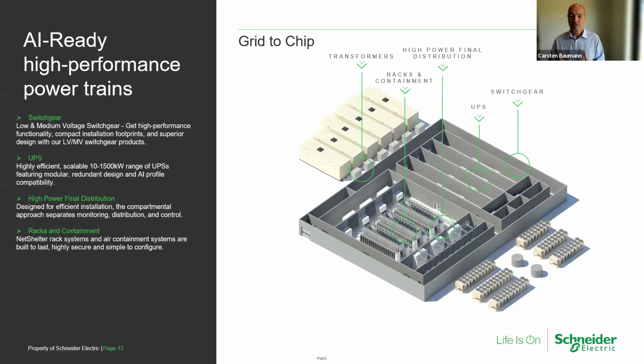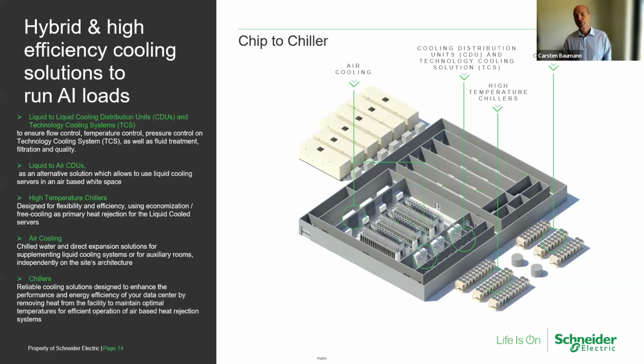And now with AI, we're actually seeing that it's not so much that the power can go out. These AI training sessions happen in about 7 minute intervals, and then they ramp down, and then they go into saving and data validation mode. However, if you do not continue to cool those chips, they can literally physically crack and destroy themselves. So therefore, there are different architectures right now where we have to put the cooling mechanism as well on these uninterruptible power supplies.